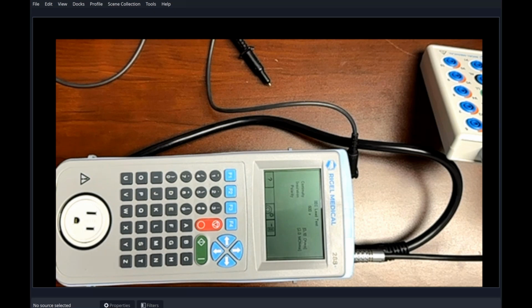Some questions that we did have come in for the webinar today are, what are the key features and capabilities of an electrical safety analyzer that you look for? So specifically for any safety analyzer, you want to make sure that it has full traceability of measurement. So that's one of the key features. You want to have accurate and repeatable results. So does it have traceability back to national standards? Are the calibration certs with that type of traceability for measurement? That's one of the most important things about test and measurement equipment, its traceability and how well the device performs when taking those measurements. You want to make sure that it's a credible device. Fortunately, all biomedical test equipment manufacturers will typically have this. This is fairly industry standard.